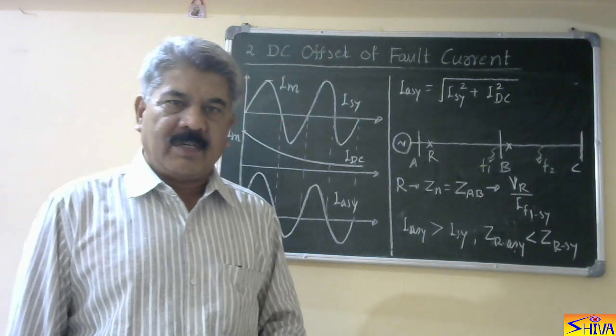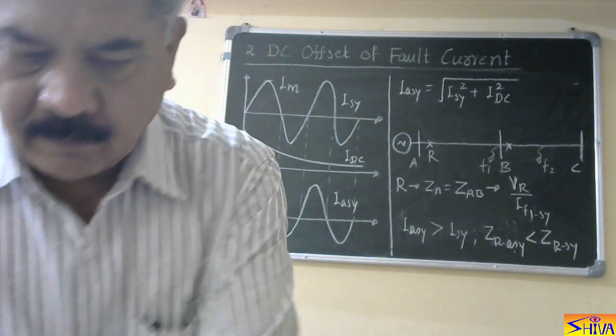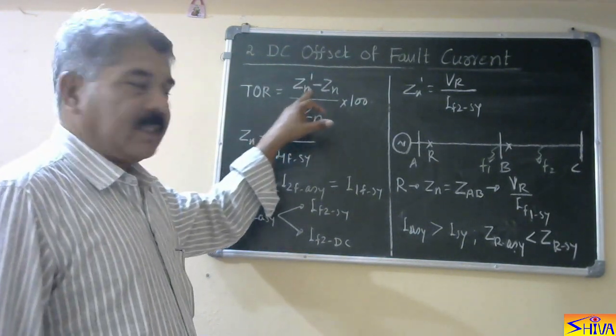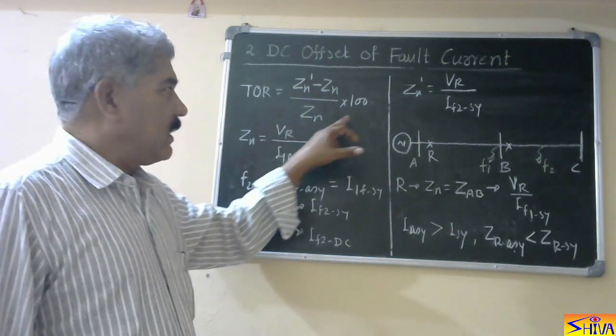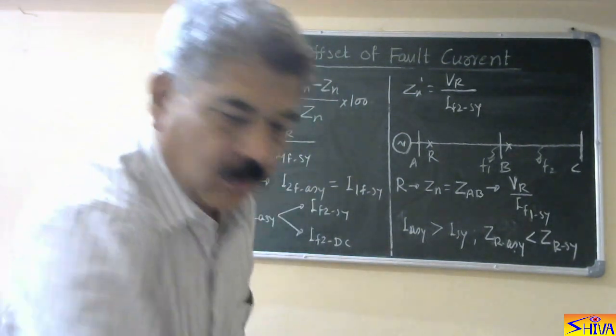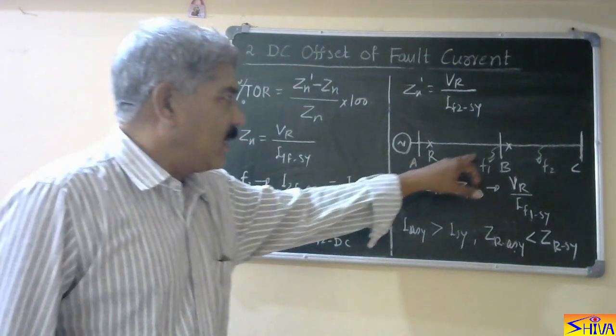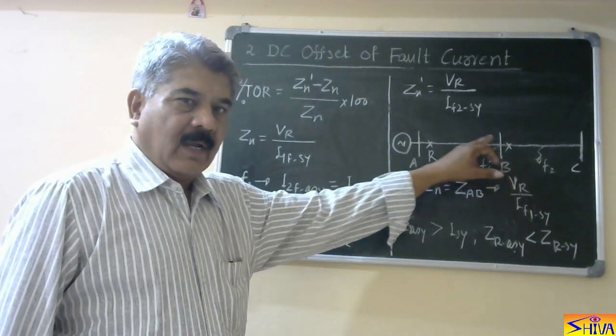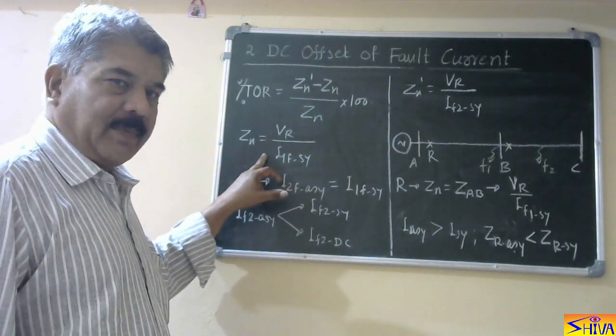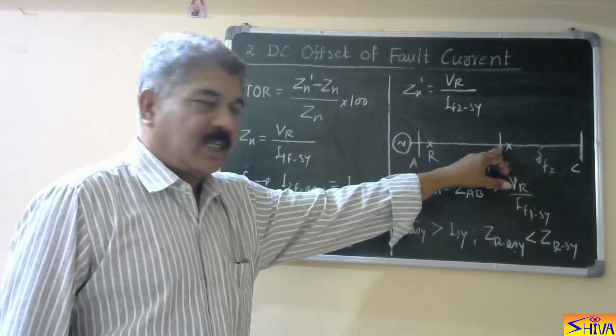Now let us find the equation for transient overreach due to DC offset of the fault current. Transient overreach is given by: (ZN_dash minus ZN) upon ZN, multiplied by 100 — this is the percentage transient overreach. ZN is Vr upon I_F1_symmetrical, where F1 is the fault at the extreme end with symmetrical fault current magnitude. So ZN, the reach or impedance setting, is Vr upon the symmetrical component of the fault current when the fault takes place at the extreme end.